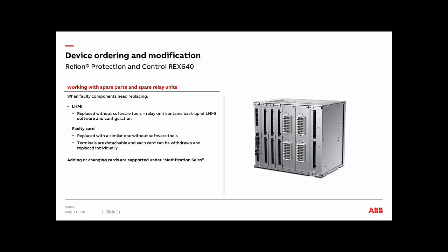So spare parts for the relay, LHMI, you can replace it without software tools. The relay itself contains a backup of the LHMI software and configuration. And of course, you can have that as well in your PCM600. So it'll be a matter of replacing the HMI and downloading configuration, which could be downloaded only to the HMI, or you can download to the whole system, relay plus HMI. But you can have the HMI loaded by itself with its configuration. That way, you don't have to touch your original relay configuration.